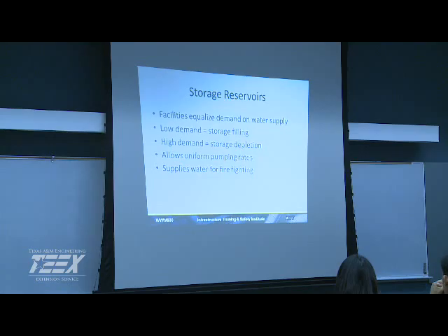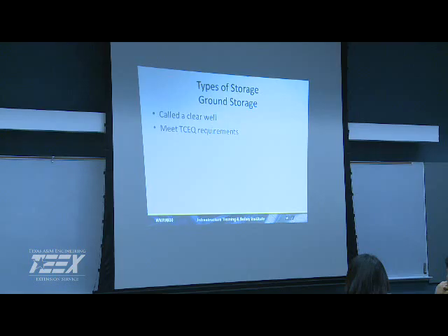So, anyways, we do have to make sure that we supply appropriate volumes at the right times, and we also need to make sure the storage is really good for our disinfection. We start talking about our CT, contact time and concentration, for our disinfectants. If it's inside a facility, it's called a clear well. Same storage device. It's just a clear well inside the fence. Outside the fence, it's a groundwater storage tank. We have to meet certain requirements.